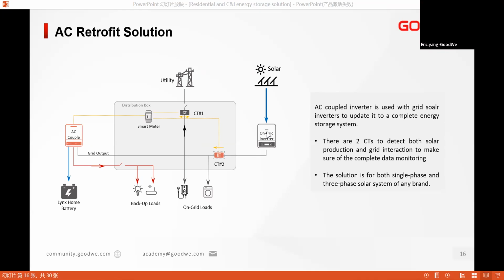So both the on-grid inverter and the AC coupled inverter can connect to the grid; we have the certification. We do not have a method to control the on-grid inverter, because the only thing the on-grid inverter needs to do is invert the DC power of the solar panel to AC power, then give that AC power to the AC coupled inverter to store it in the lithium battery. That's the only thing the on-grid inverter does, and the AC coupled inverter does not communicate with the on-grid inverter or control its working. So until now we have not met any problems with our GoodWe AC coupled inverter working with other brands' on-grid inverters, and we don't think there will be problems.